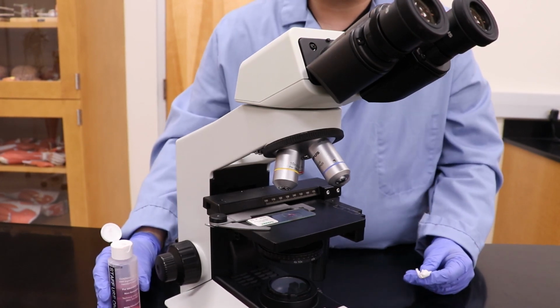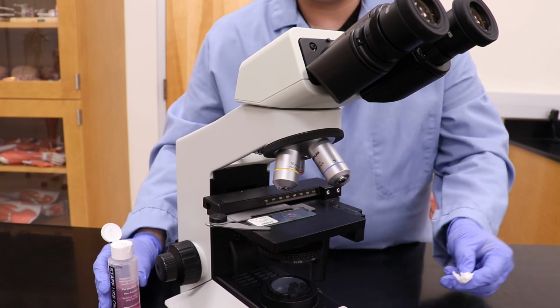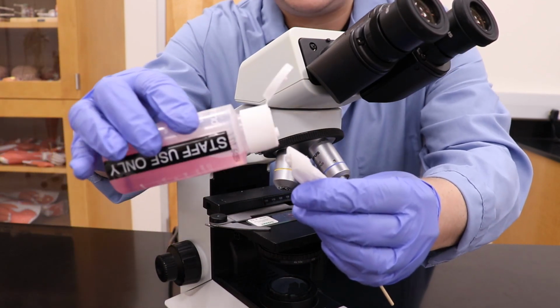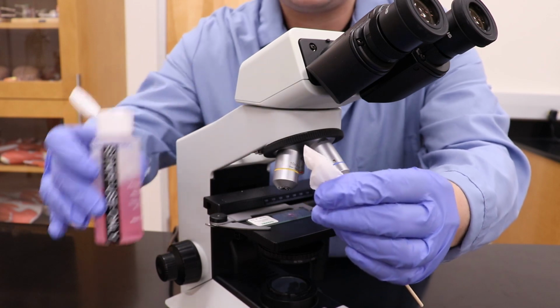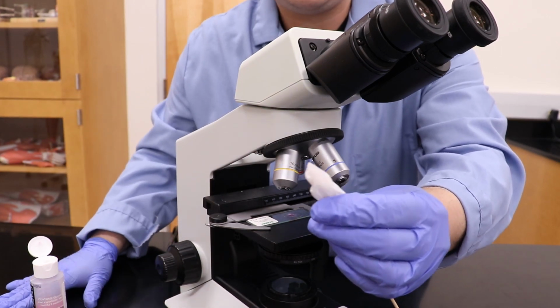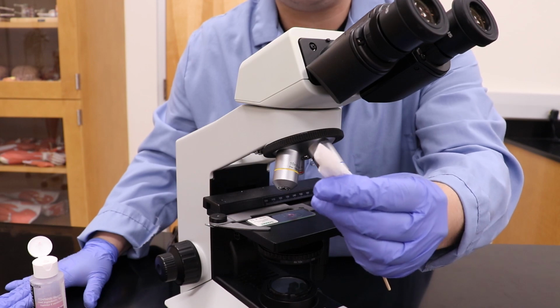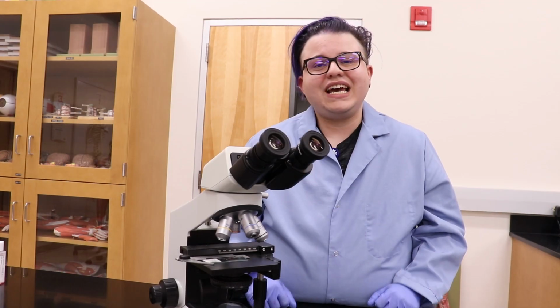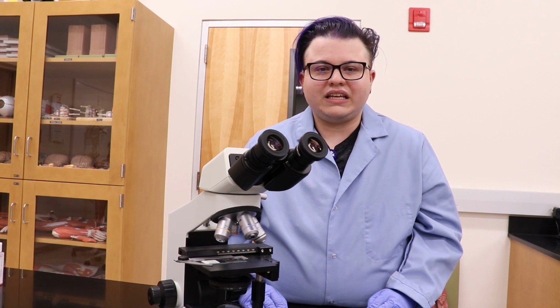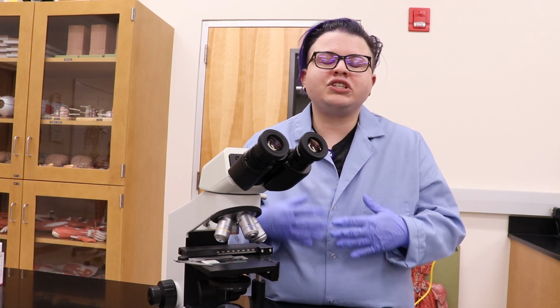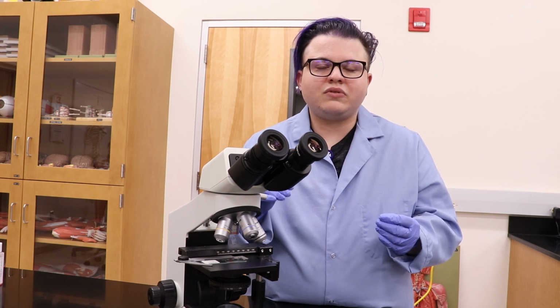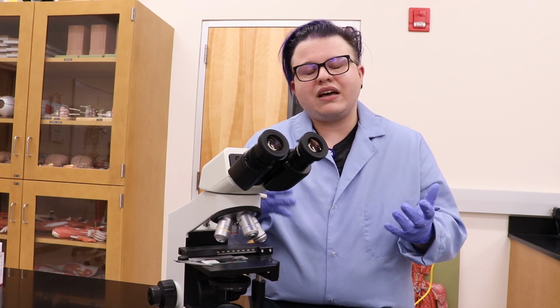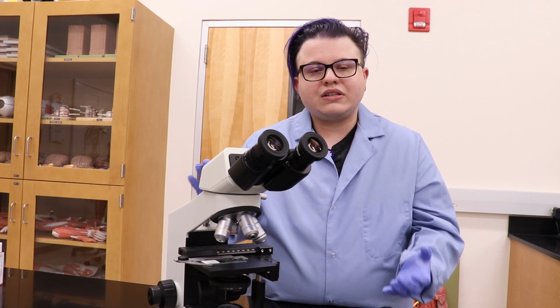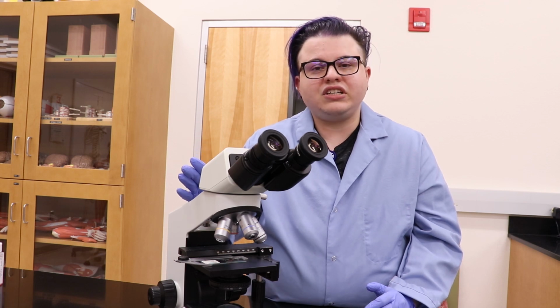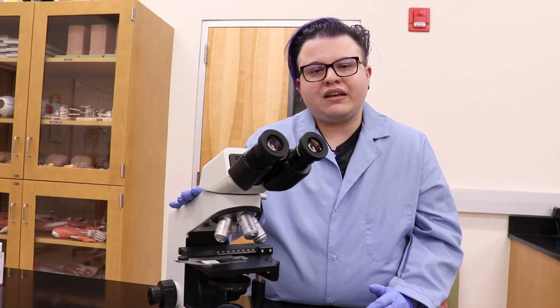If you're having issues getting an objective clean with just the lens paper, you can take your swab with the lens paper on it and dab a drop of optical lens cleaner on the tip and use that to clean the objective instead. Otherwise, you can add a drop onto the lens paper on your finger. As a note, whenever you use the lens cleaner, make sure to leave a couple seconds before checking for clarity to make sure any residual lens cleaner evaporates, because otherwise it can still appear blurry when it's actually clean. Also, if you can't remove an obstruction using the lens cleaner, set the microscope aside for staff attention.